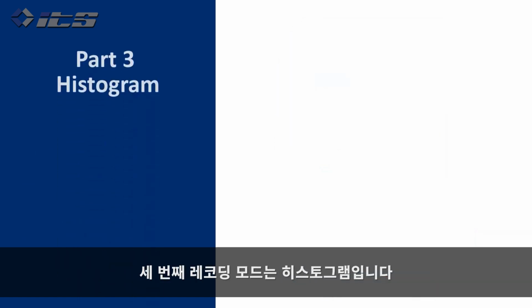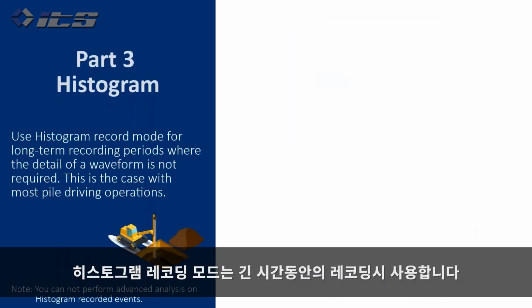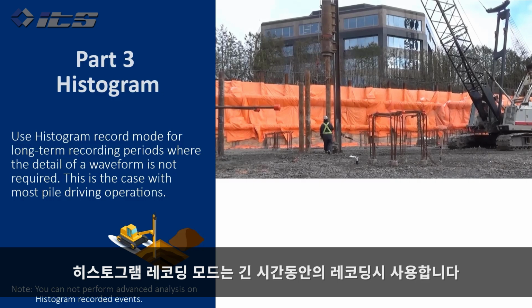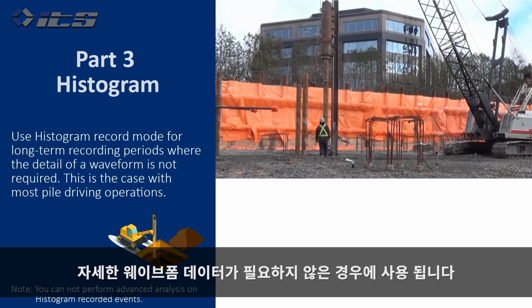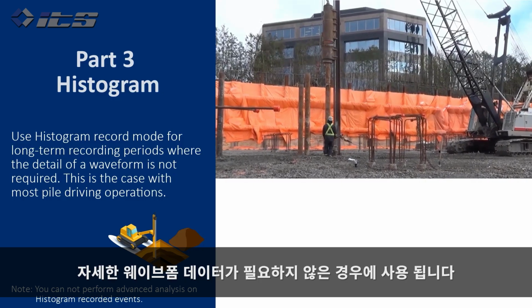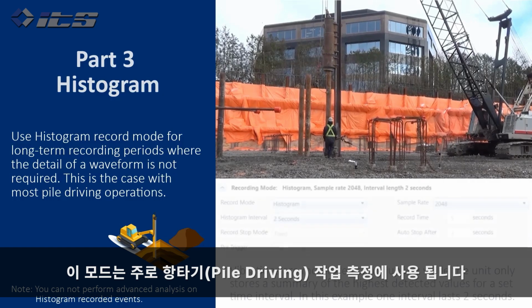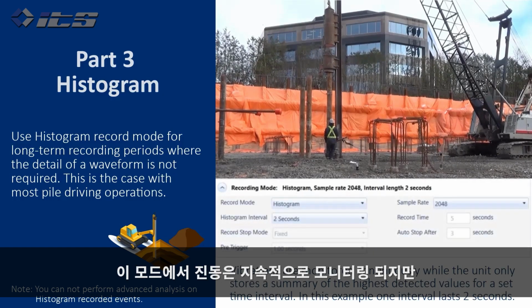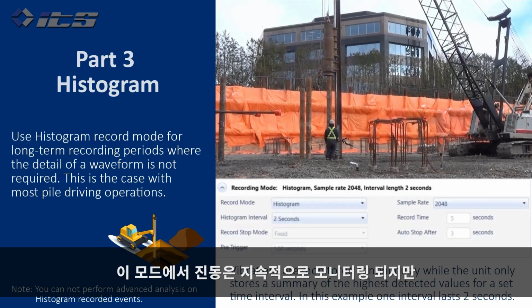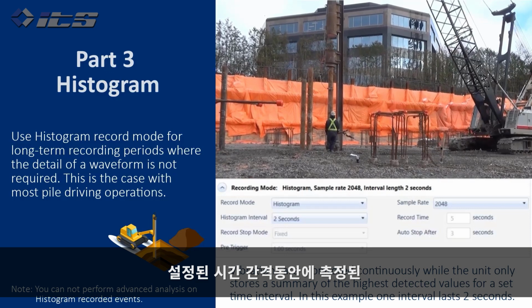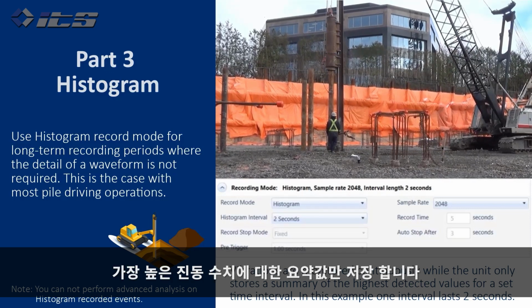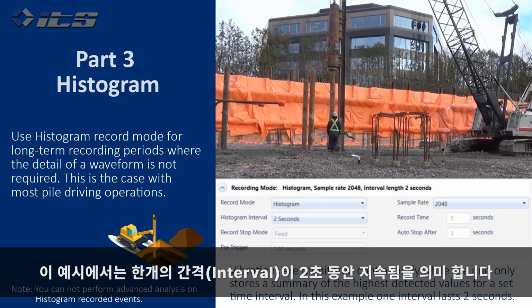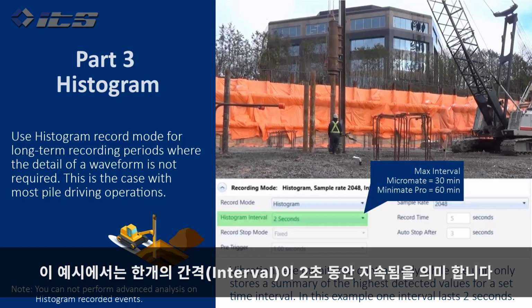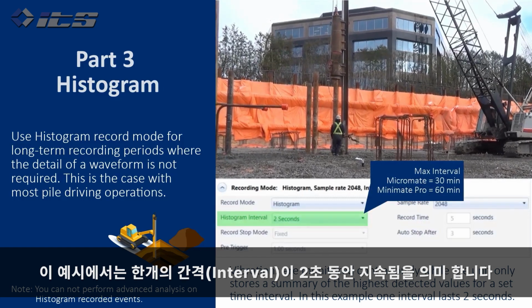The third record mode is Histogram. Use Histogram record mode for long-term recording periods where the detail of a waveform is not required. This is often the case in pile driving operations. Vibrations are monitored continuously while the unit only stores a summary of the highest detected values for a set time interval. In this example, one interval lasts 2 seconds.